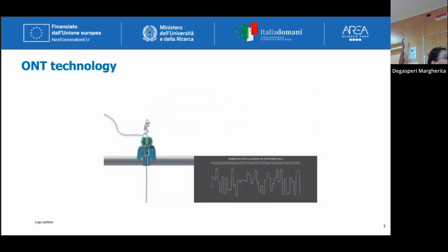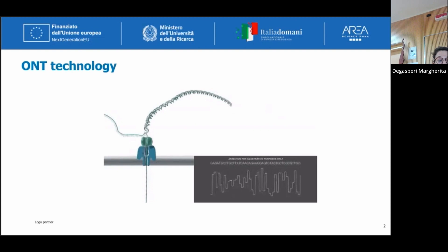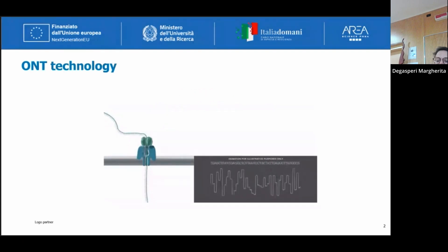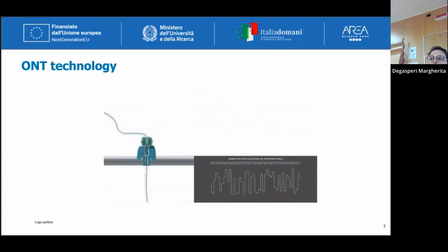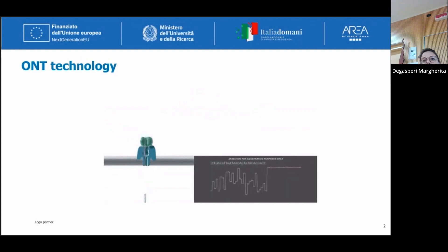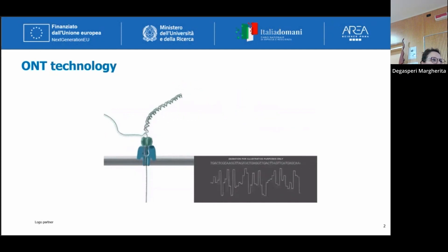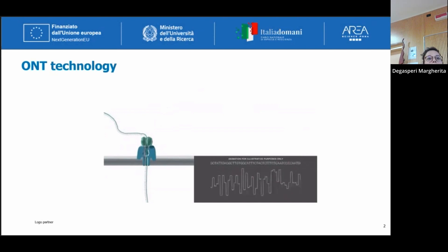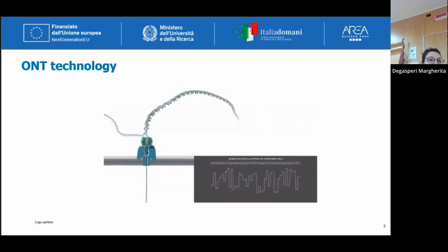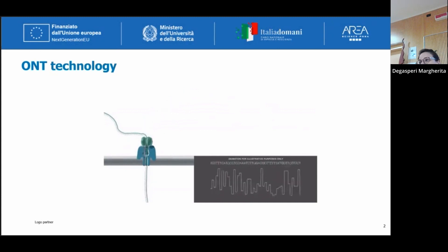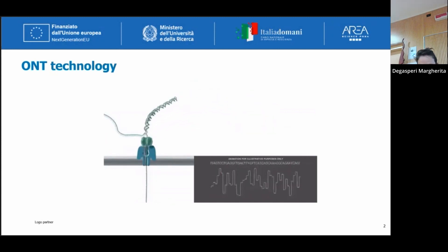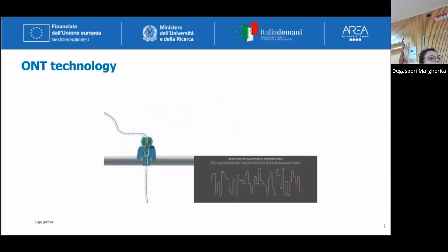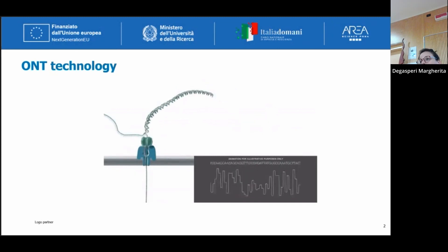Oxford Nanopore technology is based on the presence of nanopores, which act as biosensors, embedded into an electrically resistant membrane and surrounded by electrolytic fluid. During sequencing, a constant voltage is applied to obtain a current, which enables the movement of single-stranded negatively charged DNA or RNA through the pore. As the single molecule passes through the pore, a change of current is detected and correlated to the nucleotide sequence present in the sensing region. All these signals are decoded thanks to a basecaller on board, enabling identification of the nucleic acid sequence passing through the pore.